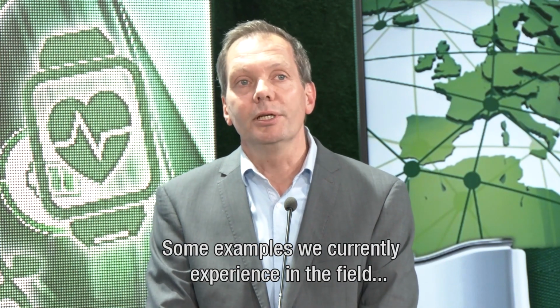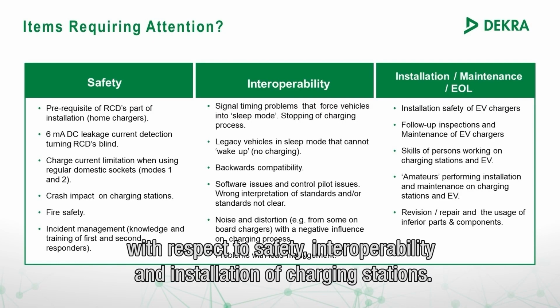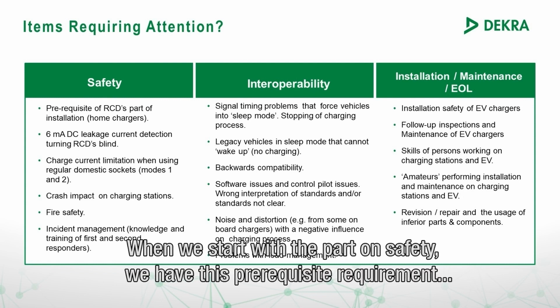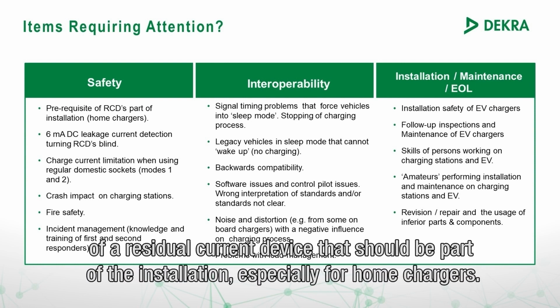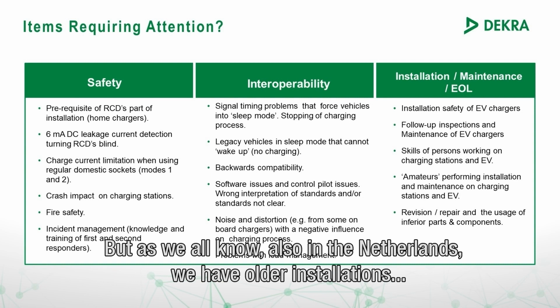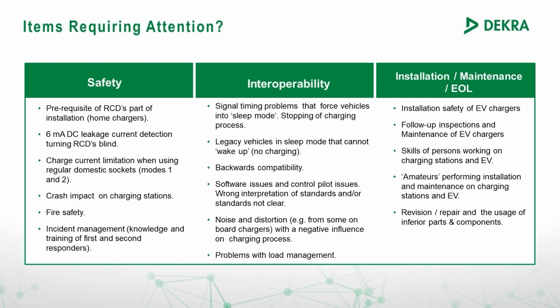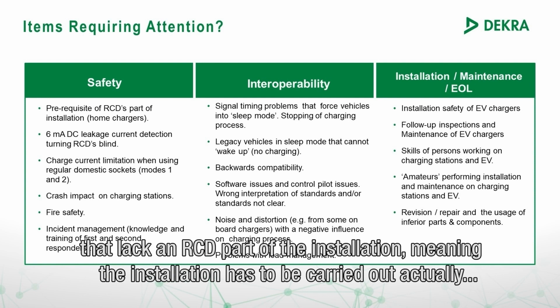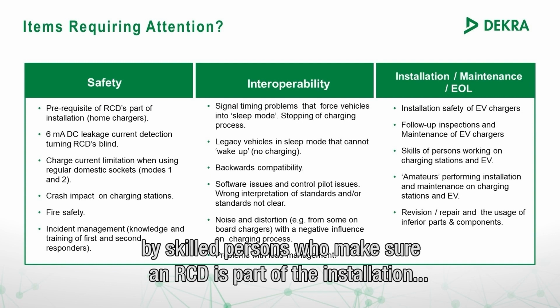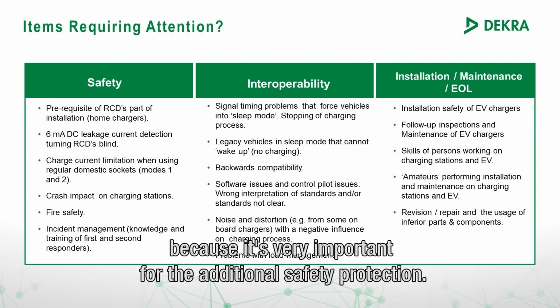Some examples we currently experience in the field with respect to safety, interoperability and installation of charging stations. Starting with safety, there is a prerequisite requirement of a residual current device (RCD) that should be part of the installation, especially for home chargers. But within the Netherlands we have some older type installations without an RCD, which means installation needs to be carried out by skilled persons who make sure an RCD is part of the installation, because it's very important for additional safety protection.